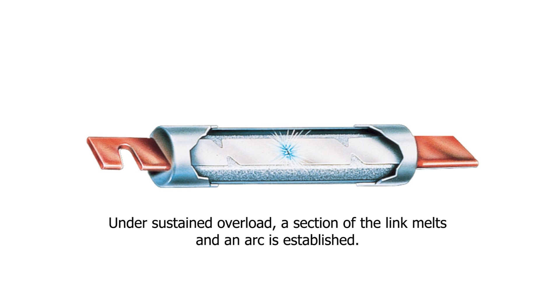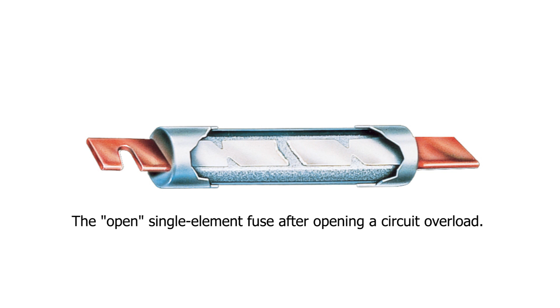The arc's resistance eventually reaches such a high level that it cannot be sustained and is extinguished. Present-day single-element fuse designs respond very quickly to overcurrents with excellent fault current component protection. However, temporary, harmless inrush currents associated with inductive loads, such as motors and transformers, may cause nuisance openings unless oversized. Therefore, they are best used in resistive circuits not subjected to inrush currents.